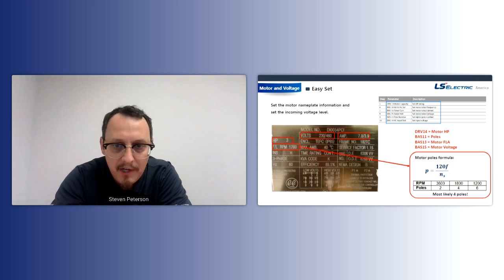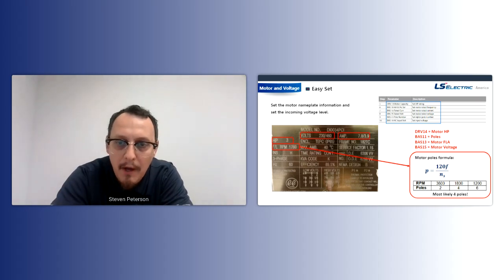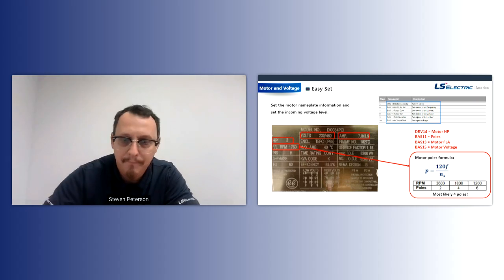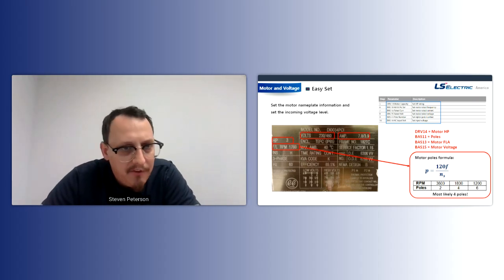So it's actually based on RPM that you can see there's a formula here, which is your motor poles is calculated by your frequency, 120, over your speed. But it's actually synchronous speed, which is generally not put on there. So we have some quick starts that I'm going to show you guys later, and we kind of give you what you need to do to pick out the motor poles. So most of the time, as I mentioned, you're going to be 4 poles or you're going to be 2 poles. Okay. So that's your motor data.